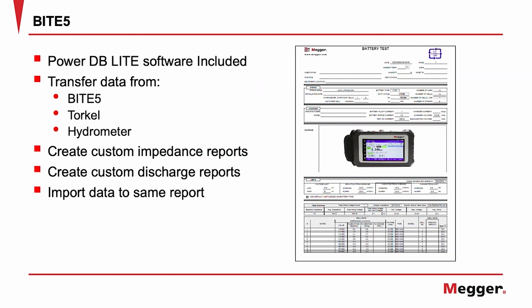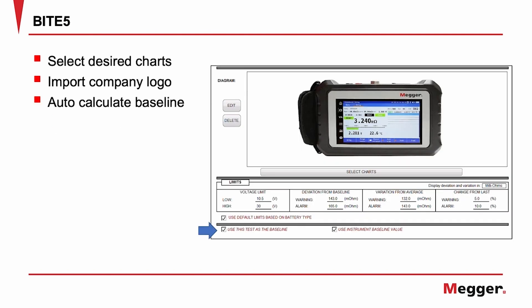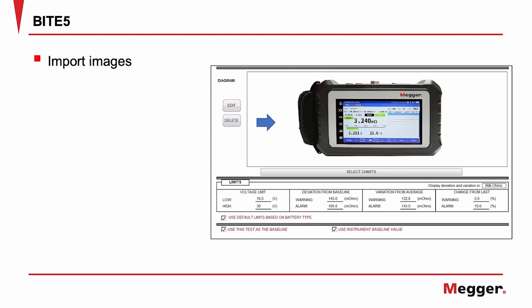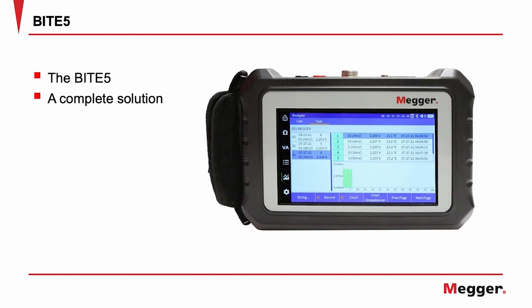Create custom impedance reports and custom discharge reports. Select desired charts and import company logos. The software will auto-calculate the baseline value for each string and auto-calculate the battery limits based on the cell chemistry. PowerDB also allows you to import images into your report, export your report as a PDF file, and export the data to a CSV file. The BITE5 — whatever type of battery, whatever type of testing you need to do, the BITE5 will do it.